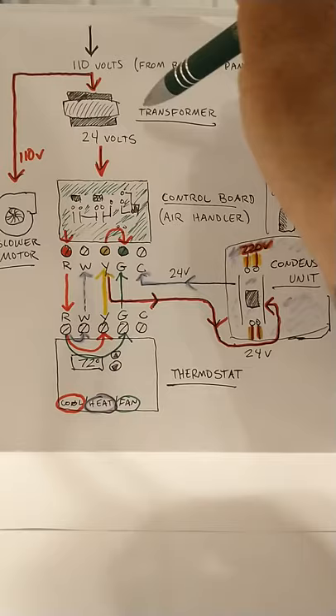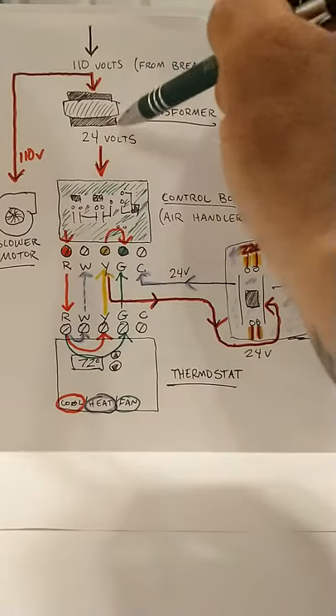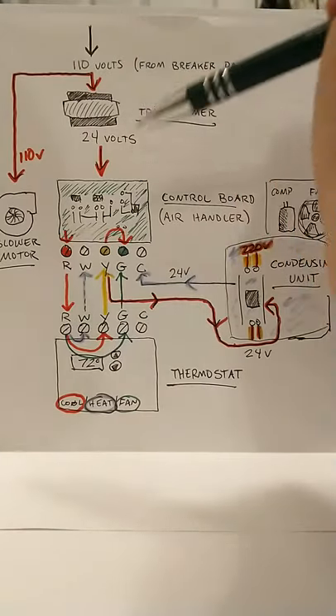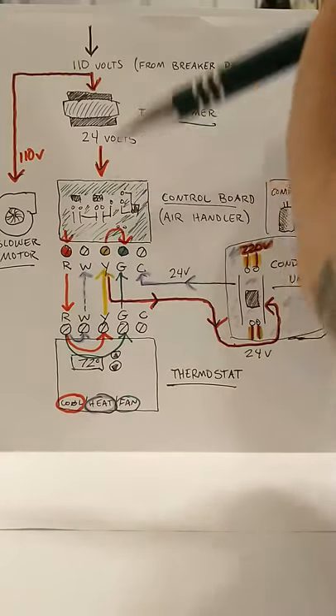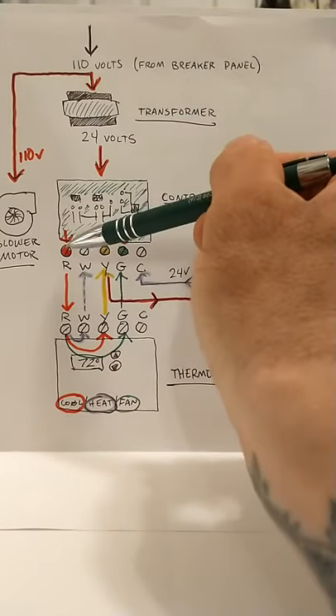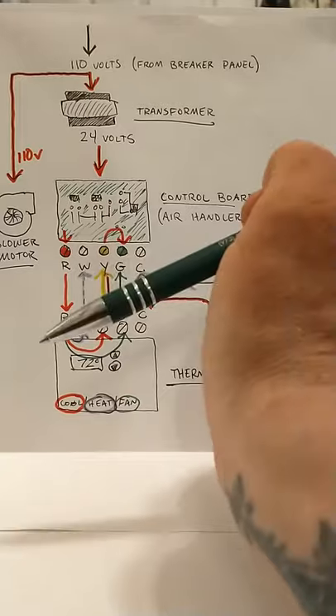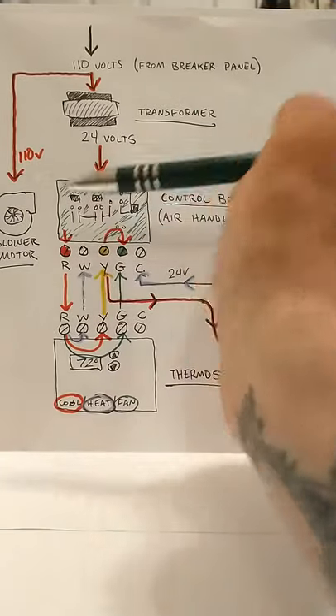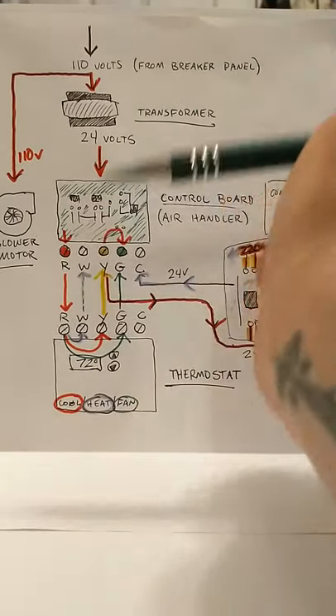Your 110 comes into the transformer, steps down to 24 volts. That 24 volts is used in the control board, and it basically all starts right here at that R terminal at your air handler. The R terminal is usually designated for 24 volts.